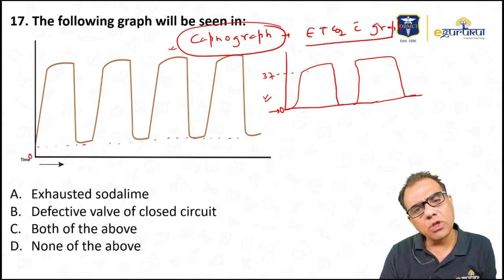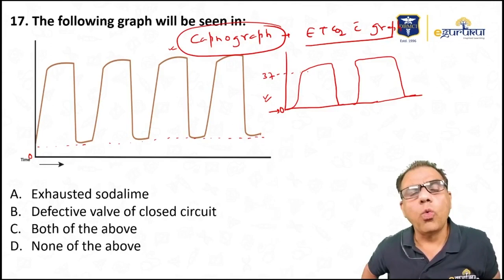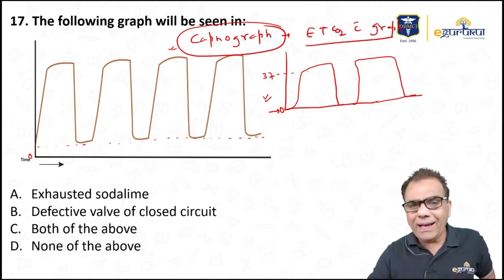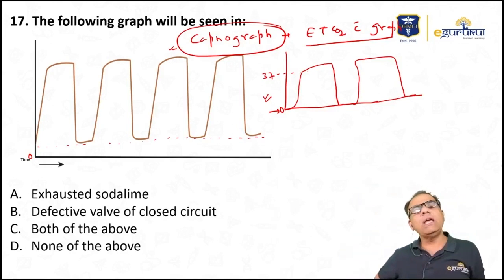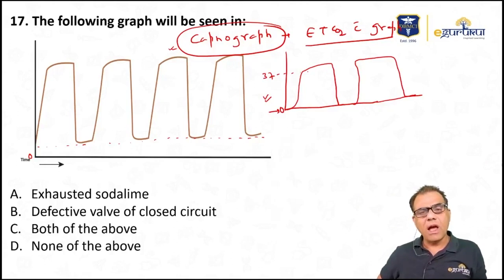It's not coming to 0, not touching the baseline. What does that indicate? That indicates that the patient is inhaling carbon dioxide. And a patient inhaling carbon dioxide means soda lime is exhausted. What will happen?